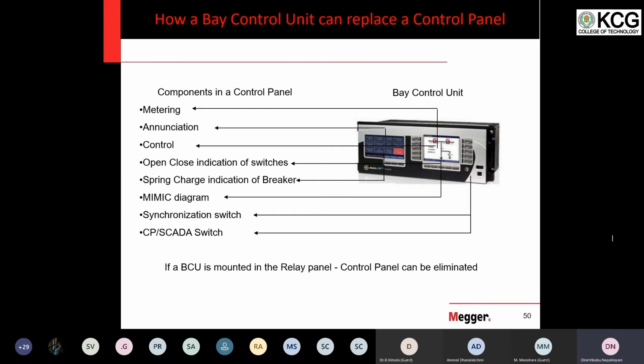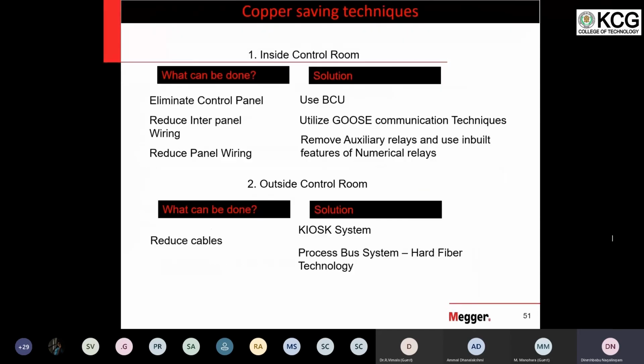And even if industries have a power shutdown, they may be penalized because they have to consume this much power. If they are not consuming because of their internal problems, they would be penalized by the utility. So when you compare all these costs, this is nothing. This is a very cheap solution compared to replacing a control panel with a BCU. This is how it works. This is the first option, use a BCU. The second, reduce interpanel wiring, eliminating the interpanel wire. We are going to use bus communication. So let us see.